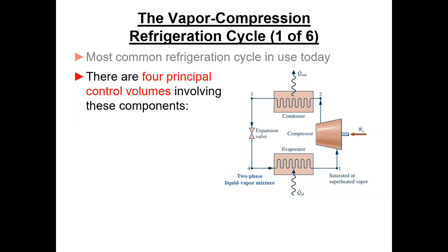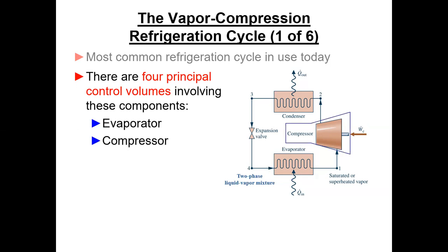The evaporator is where the cooling effect occurs. If this is an air conditioning system in your house, return room air is blown across a coil that has cold refrigerant in it. As heat transfers from the warm air to the refrigerant, the refrigerant boils off. It's mostly a cold liquid when it enters the evaporator, and we complete the phase change as refrigerant flows through the coil.